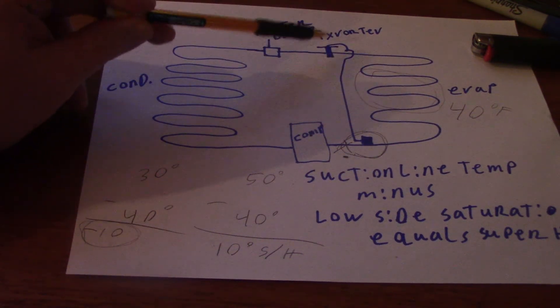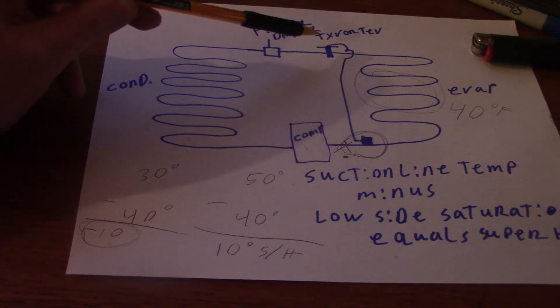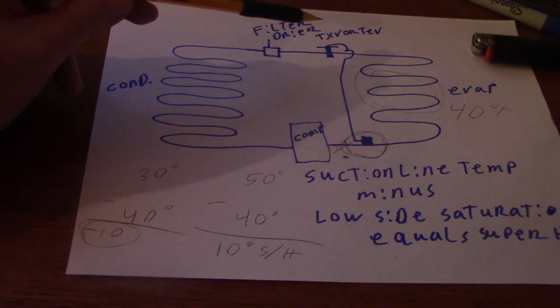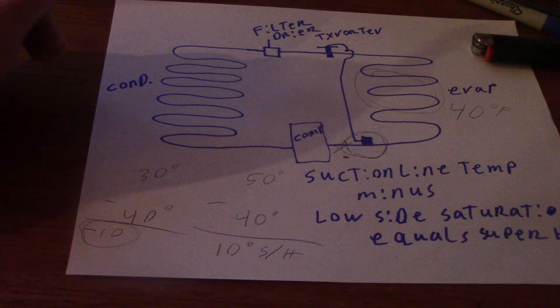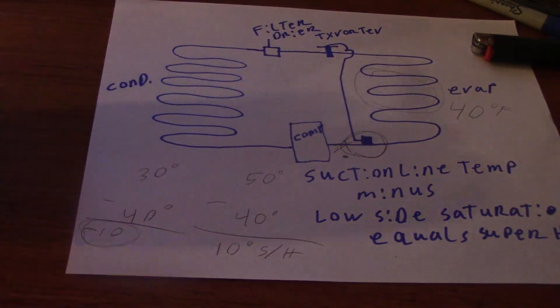I'll give you a little tip here. If you have too high of superheat with a TXV, either A, the screen's clogged up, or B, the TXV is malfunctioning, and it just can't adjust to add the refrigerant here.